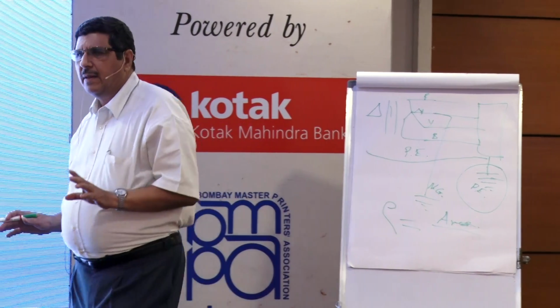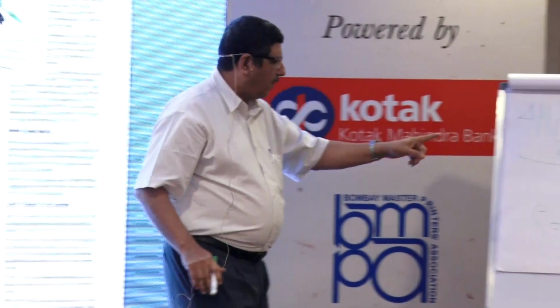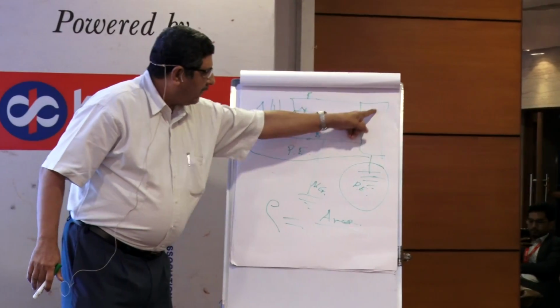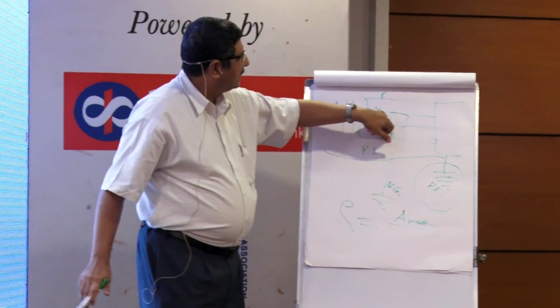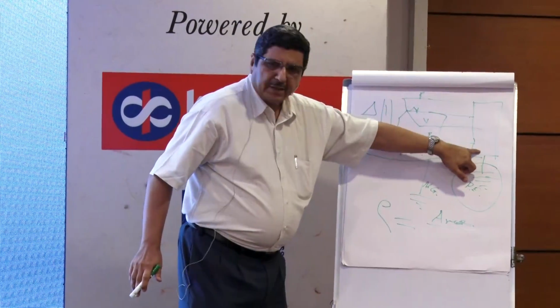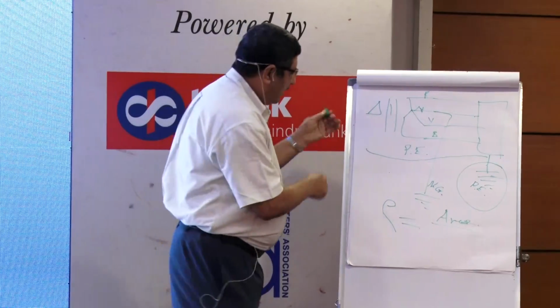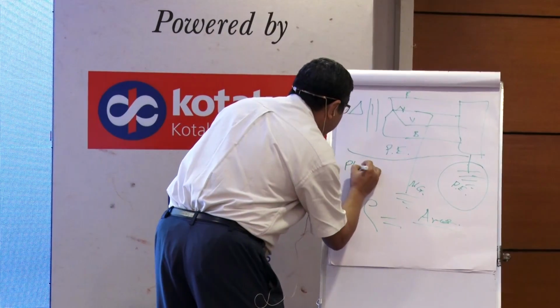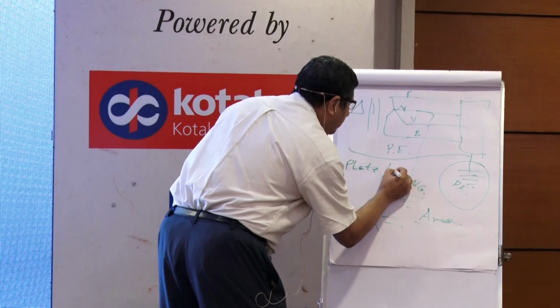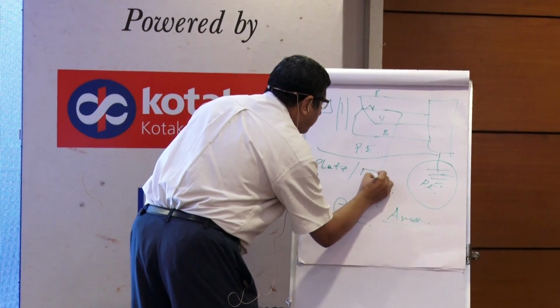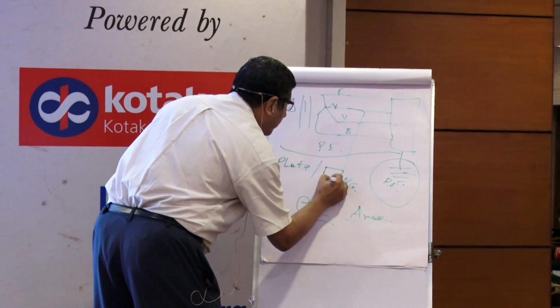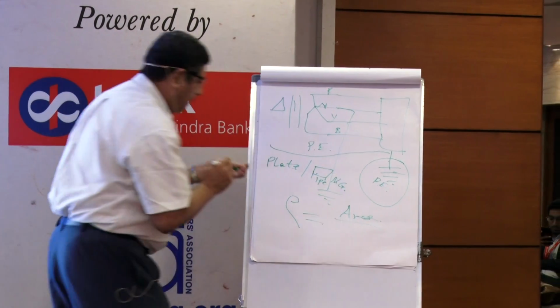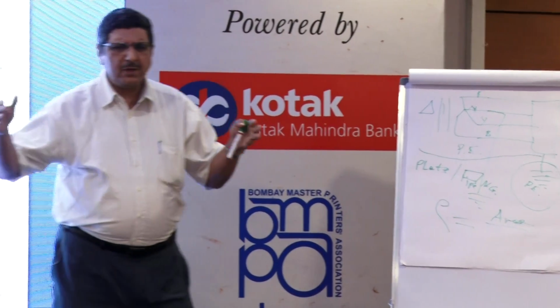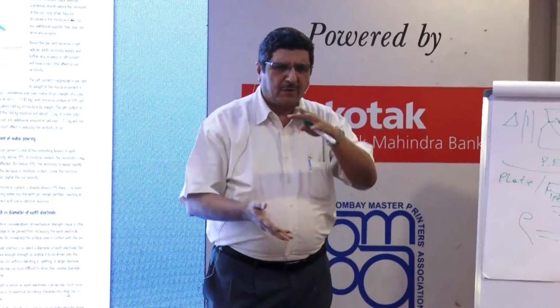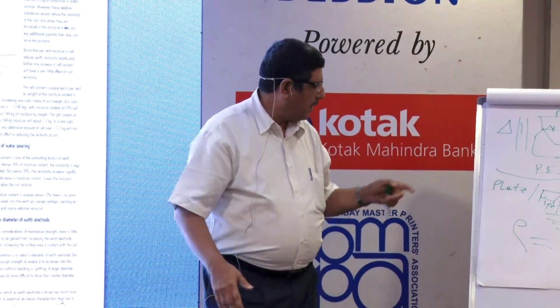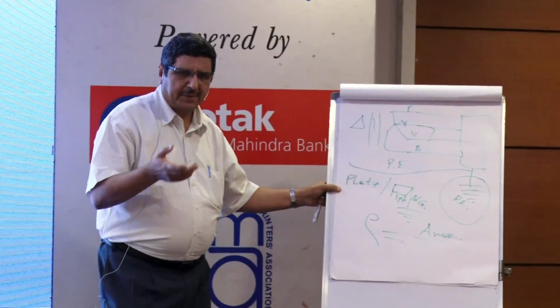You can take tappings from there with copper wires and all that. It's not so important, but this grounding is very important for your equipment which has got electronics. As Mr. Shridhar was saying, we need a neutral and we need the earthing. So two methods are there: one is plate earthing and the other one is pipe earthing. Now when I say plate earthing, we normally use a copper plate of say 1 foot by 1 foot, or maybe 1 foot by 1.5 foot, and it will be 3 mm thick or 6 mm thick.